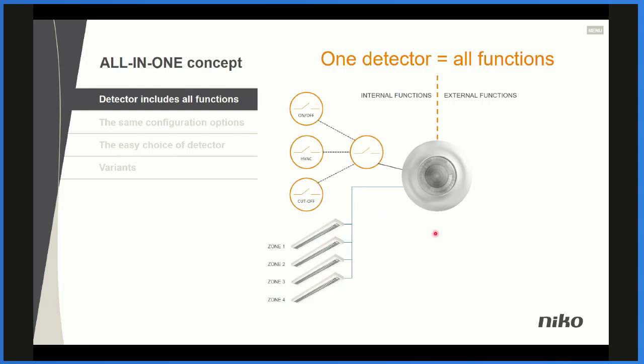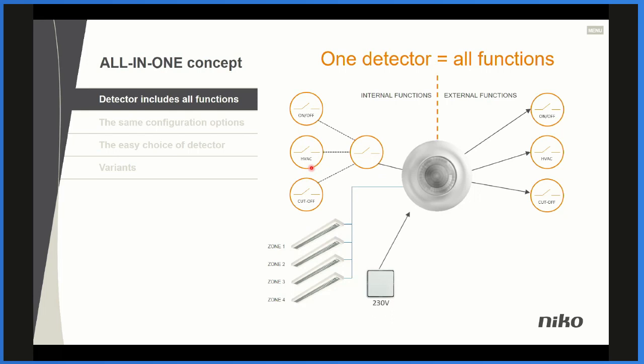There's one relay built in, but if you want more control, that means you have both non-dimmable lighting and HVAC, we can put a standard DALI relay on the DALI bus that has exactly the same functionality as the built-in relay. If you want to control it, that means override it, we can connect a 230 volt push button in order to override it or to manually dim.